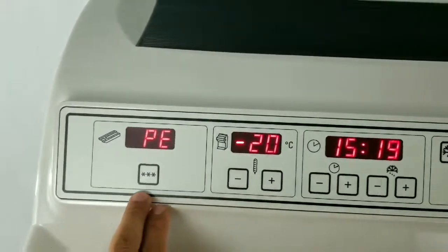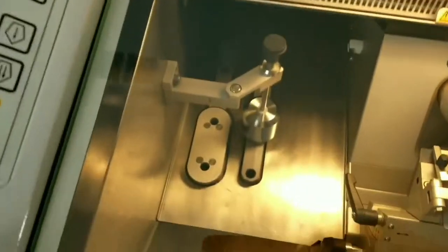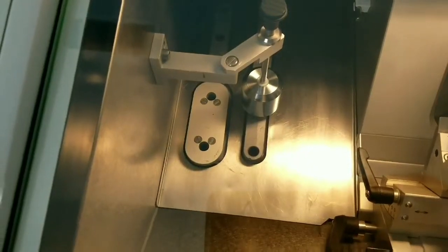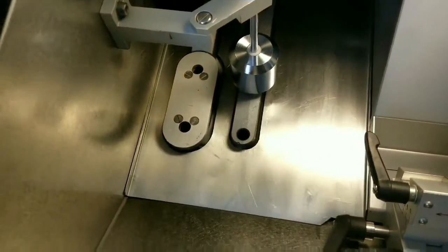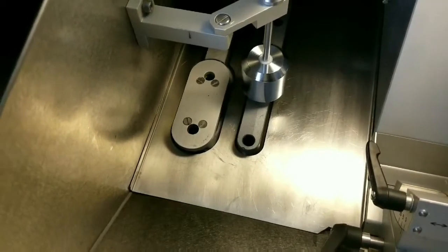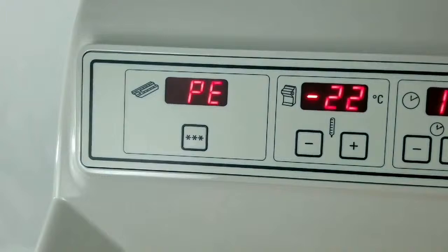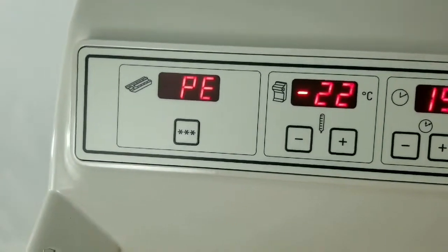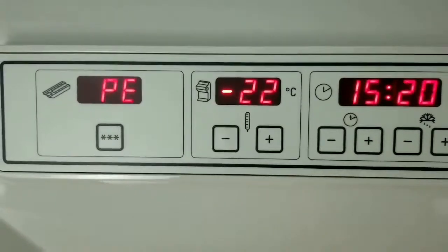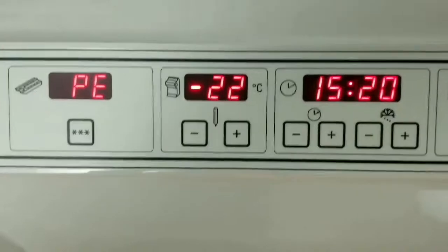This is the Peltier — a thermoelectric cooler located on the quick-freeze shelf, underneath these two stations for your tissue chucks. When you press that button, it will come on for 10 minutes and the temperature will actually get 10 degrees colder than the actual cryo chamber temperature.